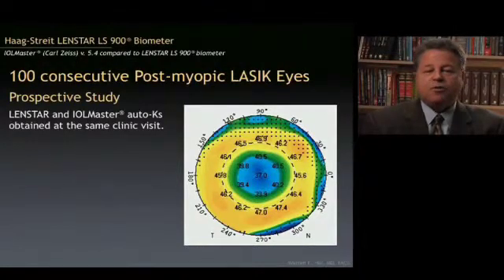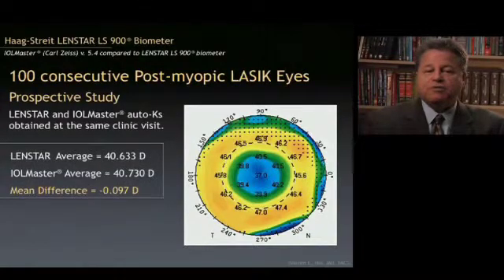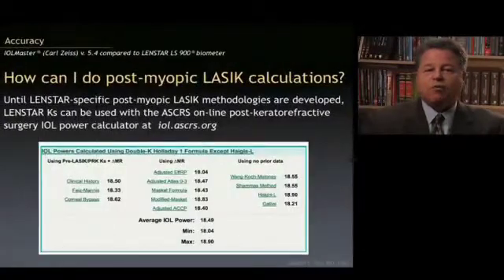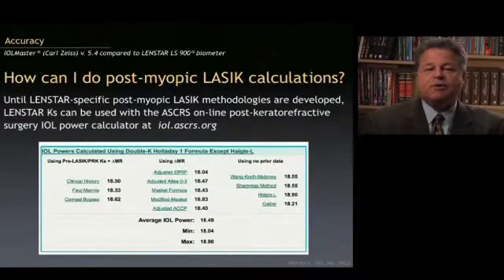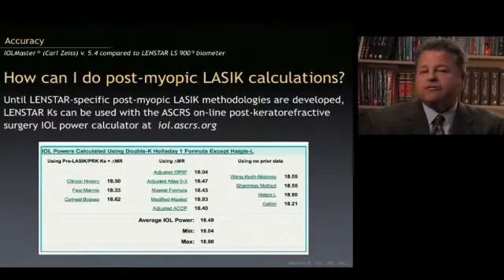What about eyes that have had prior post-myopic LASIK? There are a number of calculation methodologies available, most using either topography or IOL Master K readings. In our practice we did a study with 100 consecutive post-myopic LASIK eyes and found that the difference between the LenStar and the IOL Master was less than one-tenth of a diopter. This means it is possible to use the ASCRS calculator for post-myopic LASIK calculations, and the ASCRS online post-refractive surgery calculator can be used with confidence with this instrument.